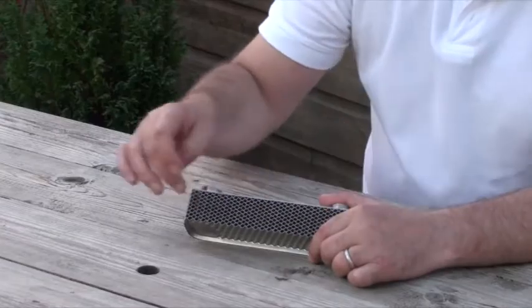Now, your water, on the other hand, will come through on the other side of this heat exchanger, which has two other holes. The water will come through and travel through these layers backwards and forwards in 2, 4, 6 and 8. As that water travels through, it is heated above and below by this boiling hot loop of water. Now, as water travels through, there is natural sediment in that water. You will hear of other devices, such as magnetic devices and so on, that will attract the pollutants and metal particles that are in the water. But what you'll find is there's also just sediment, and it's very, very small, but it will gather over time.